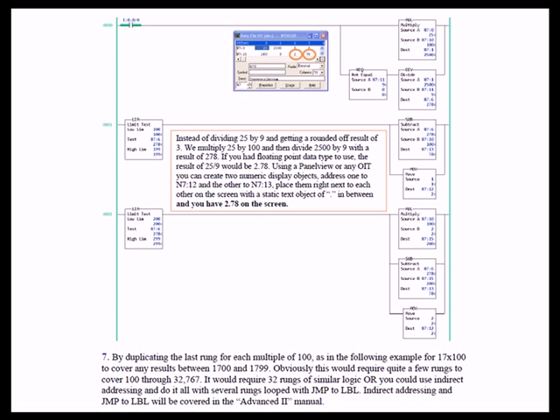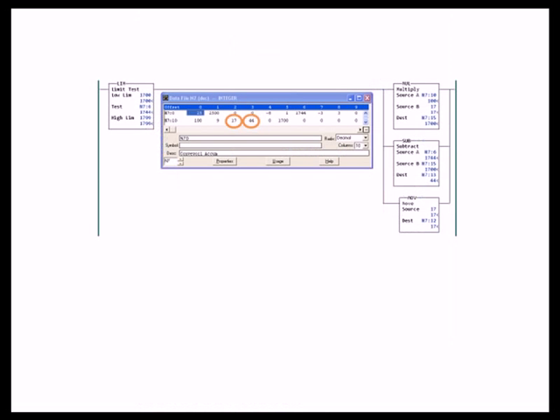By duplicating the last rung for each multiple of 100, as in the following example, you can continue this process as high as you want to go. In order to use this type of logic, you would have to create a rung for each range of 100 counts. In this rung, we are covering the test values for N7:4 from 1700 to 1799. So if our value is between 1700 and 1799, then this rung will execute. All the other rungs will not execute because their limit test is for another range of 100 counts. So here we end up with two values, 17 and 44, and then we could display that as 17.44. In order for this to work, you would have to have a rung in logic for every range of 100 counts all the way from 0 to 32,767.